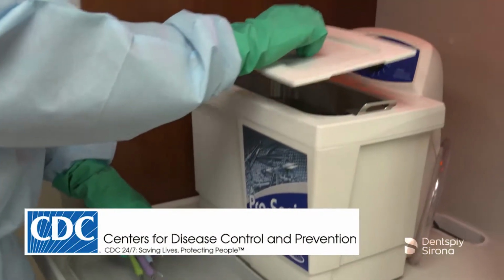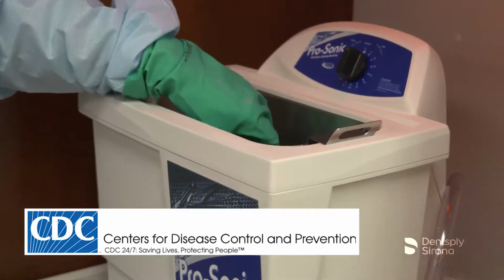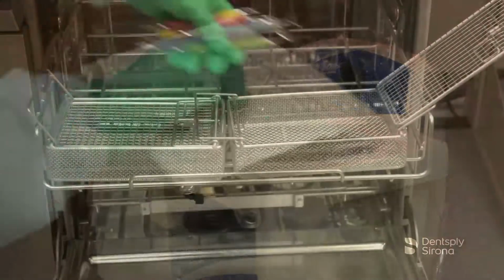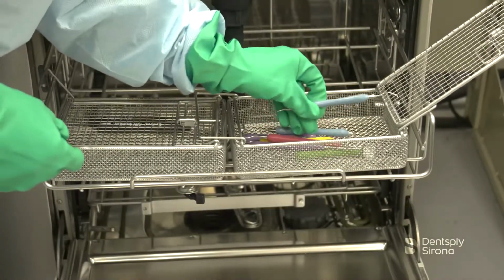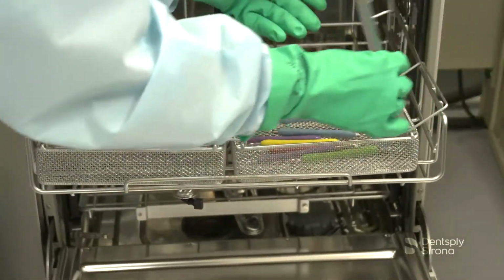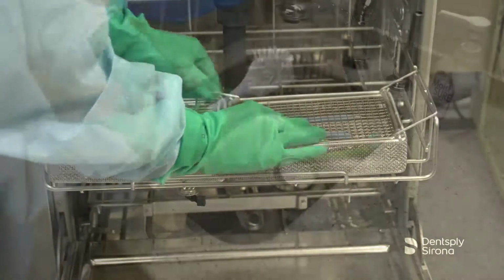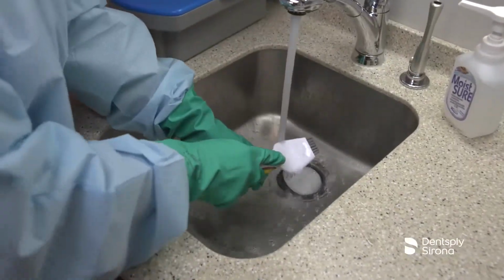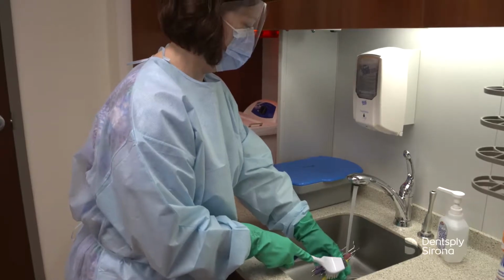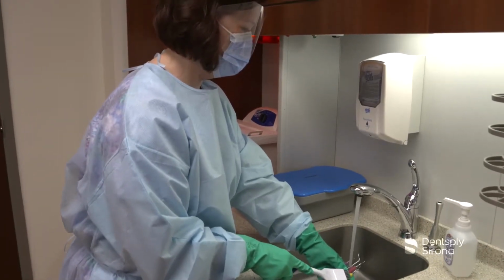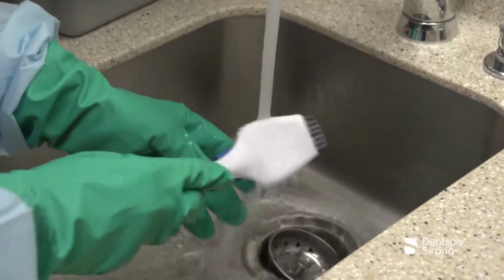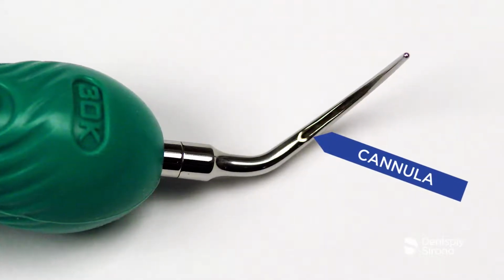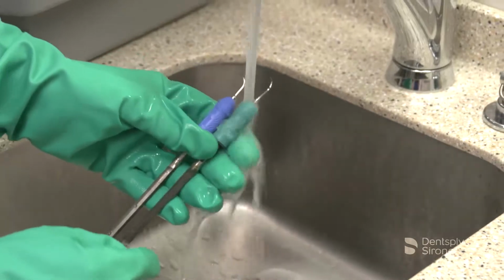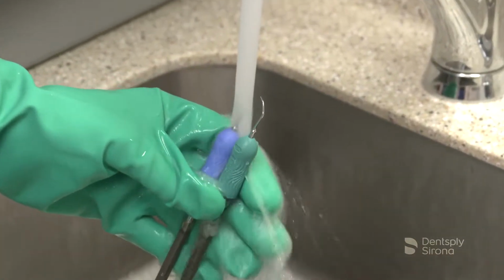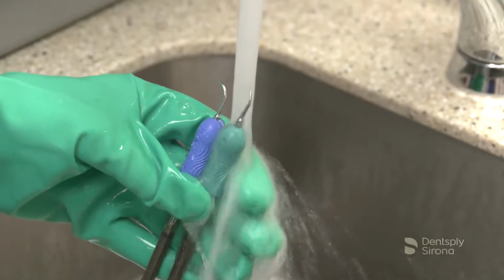The CDC recommends the use of automated cleaners. Manual cleaning and/or scrubbing should be avoided to reduce the risk of injury or exposure to the clinician. When an ultrasonic bath or automatic instrument washer are not available for instrument cleaning, manual cleaning is then utilized. Instruments should be scrubbed low in a sink at arm's length, utilizing a long-handled brush with a surfactant or detergent under running water. When manually cleaning Cavitron inserts, pay particular attention to the holes and cannulas to remove debris. Rinse under running water for 30 seconds to remove the cleaning agent. A disposable syringe may be used to rinse the holes or cannulas.